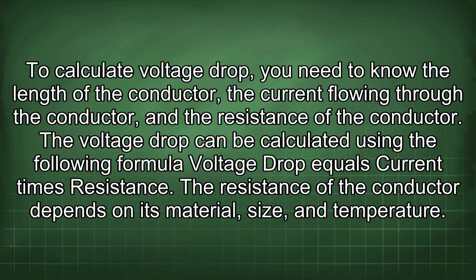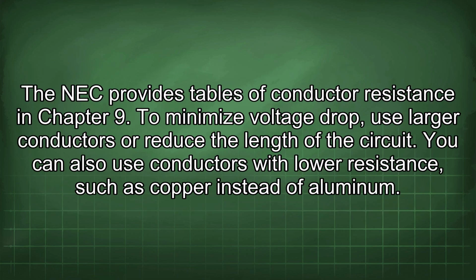To calculate voltage drop, you need to know the length of the conductor, the current flowing through the conductor, and the resistance of the conductor. The voltage drop can be calculated using the following formula: voltage drop equals current times resistance. The resistance of the conductor depends on its material, size, and temperature. The NEC provides tables of conductor resistance in Chapter 9.